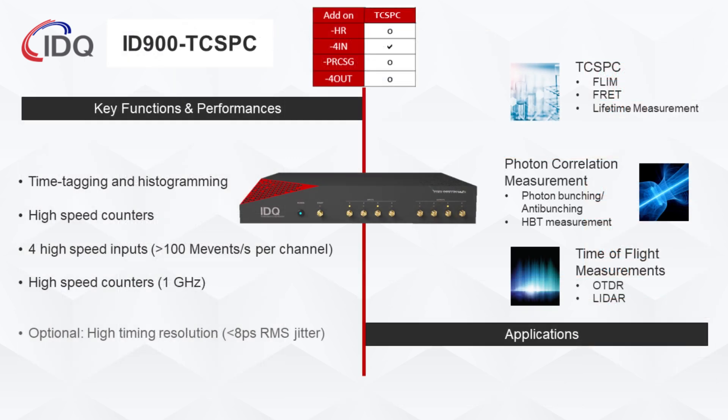The ID900TC SPC is designed for time-correlated single-photon counting measurements, and it has the same functionality as a classical time-tagger, enabling you to use the four inputs for histogramming, time-tagging, and counting. It is optimized for dedicated TC-SPC applications such as FLIM, FRET, lifetime measurement, or other photon-correlation measurements including photon-bunching/antibunching or Hanbury-Brown-Twiss measurements.